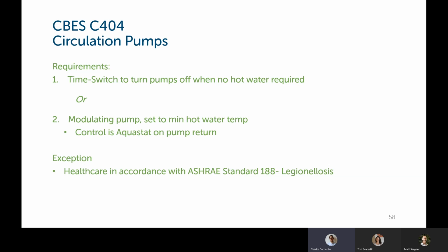And there is an exception here for healthcare facilities, where Legionnaires' disease could be an issue in having sort of stagnant water not circulating through the building. You need to meet the requirements of ASHRAE standard 188 in healthcare facilities.